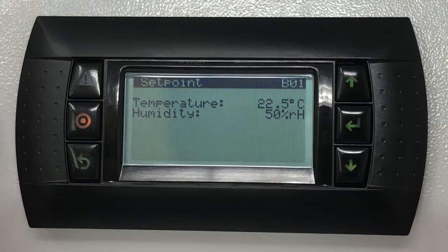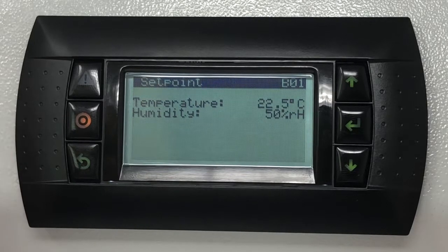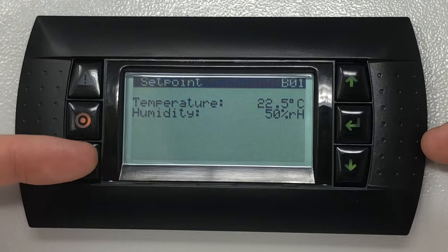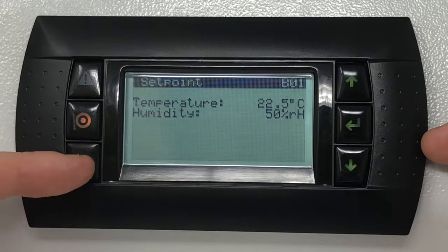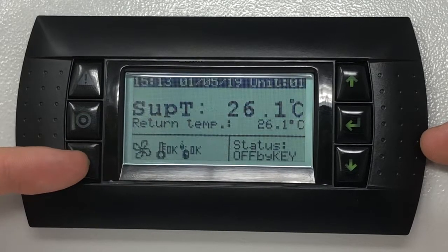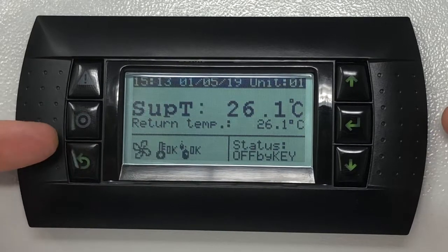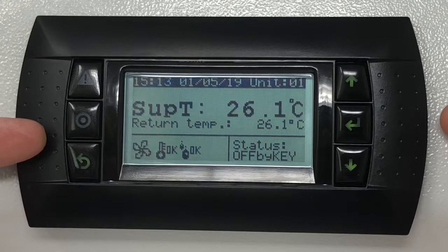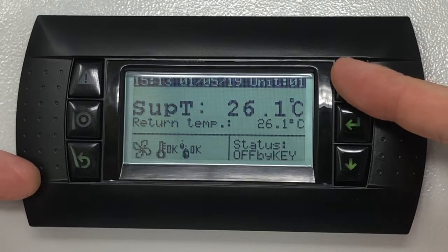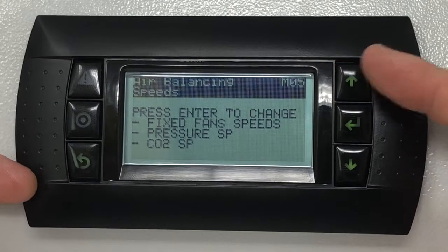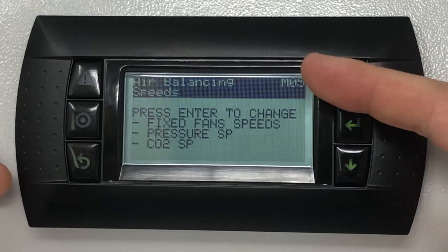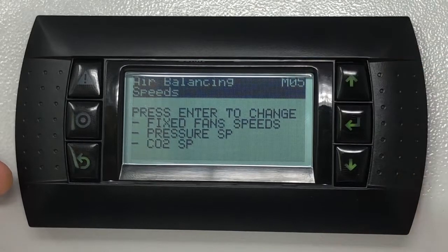To adjust the fan speed, press the escape button on the bottom left hand side of the display a few times to make sure you return back to the home screen. Press the up key once to display the air balancing speed screen marked as M05 on the top right hand corner.